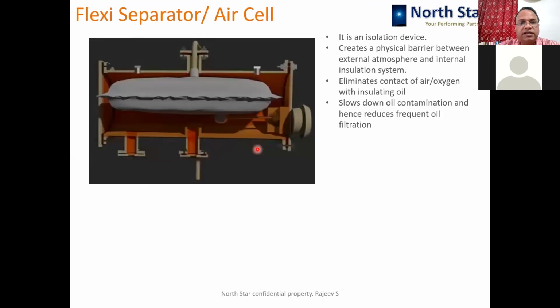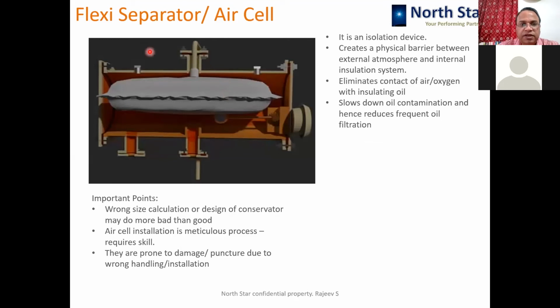Okay. Third thing is the flexi separator or air cell, which is the advancement over the plain breather. In this case, the breather is mounted on the air cell. This is the outlet of the air cell, and this is the breather pipe. So the breather is mounted on this, and that's how the external air doesn't come into contact with the oil inside the conservator, and your oil practically remains out of touch from the external moisture. So now when you put this air cell in place, the only moisture you have to deal with in the transformer is the internal moisture which is getting generated in the transformer.